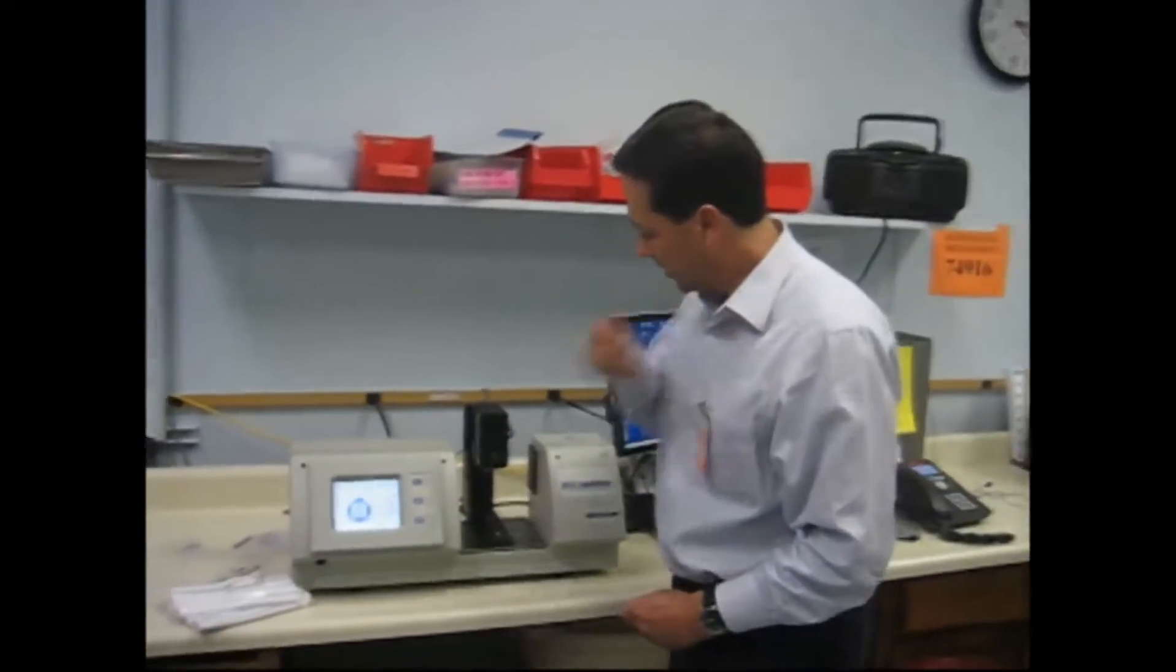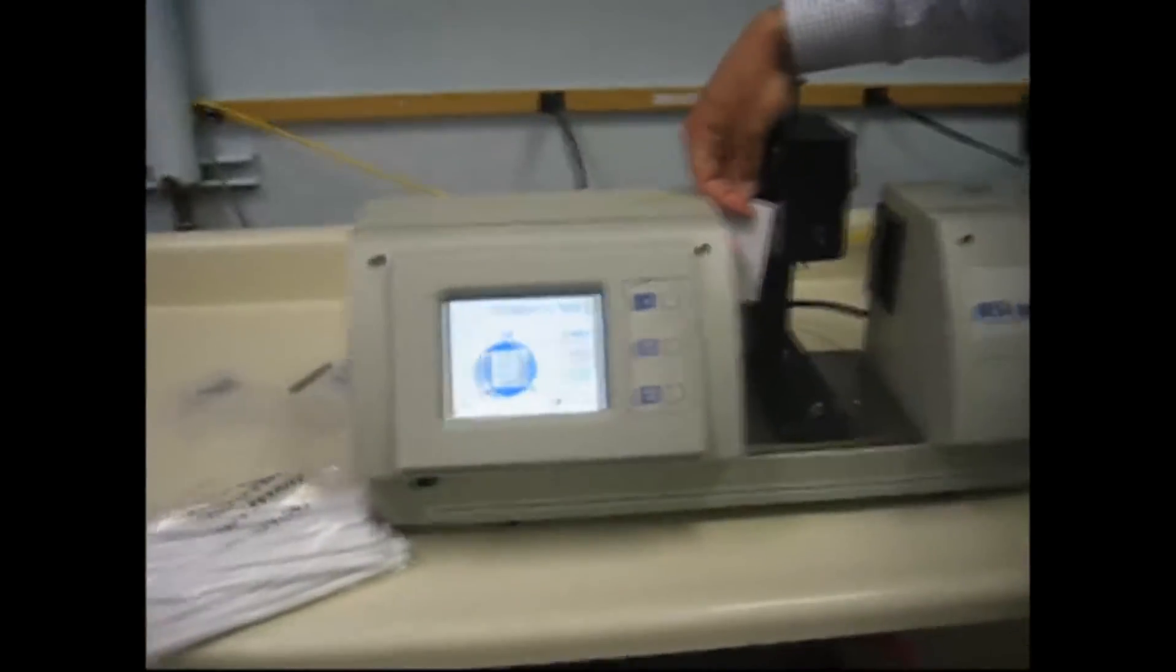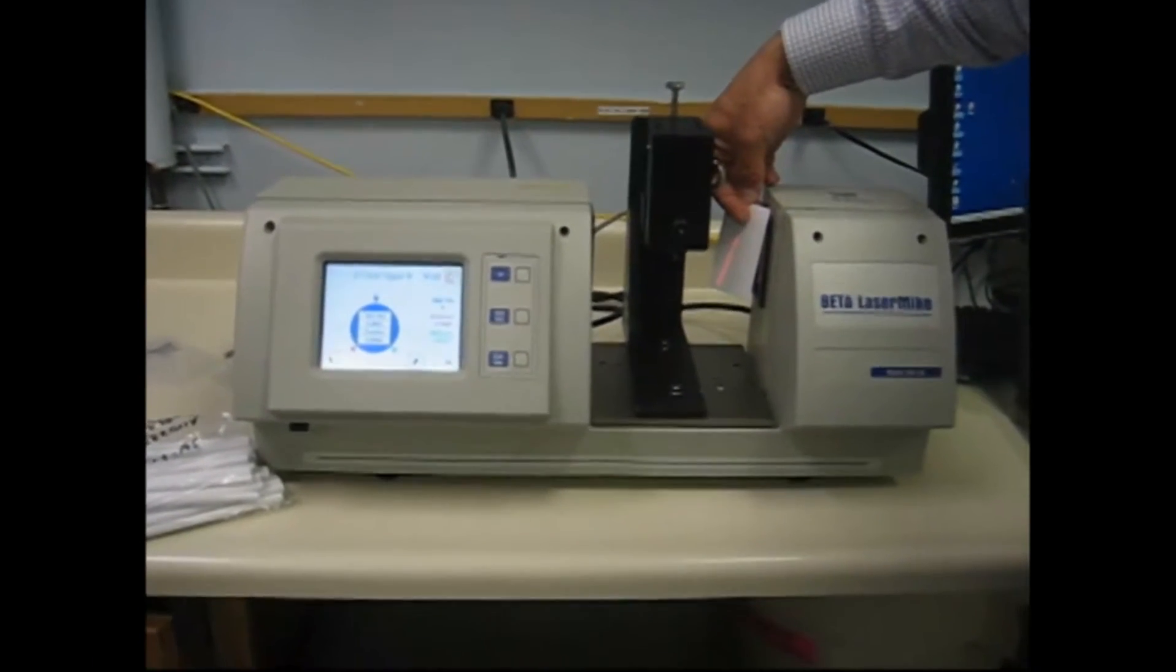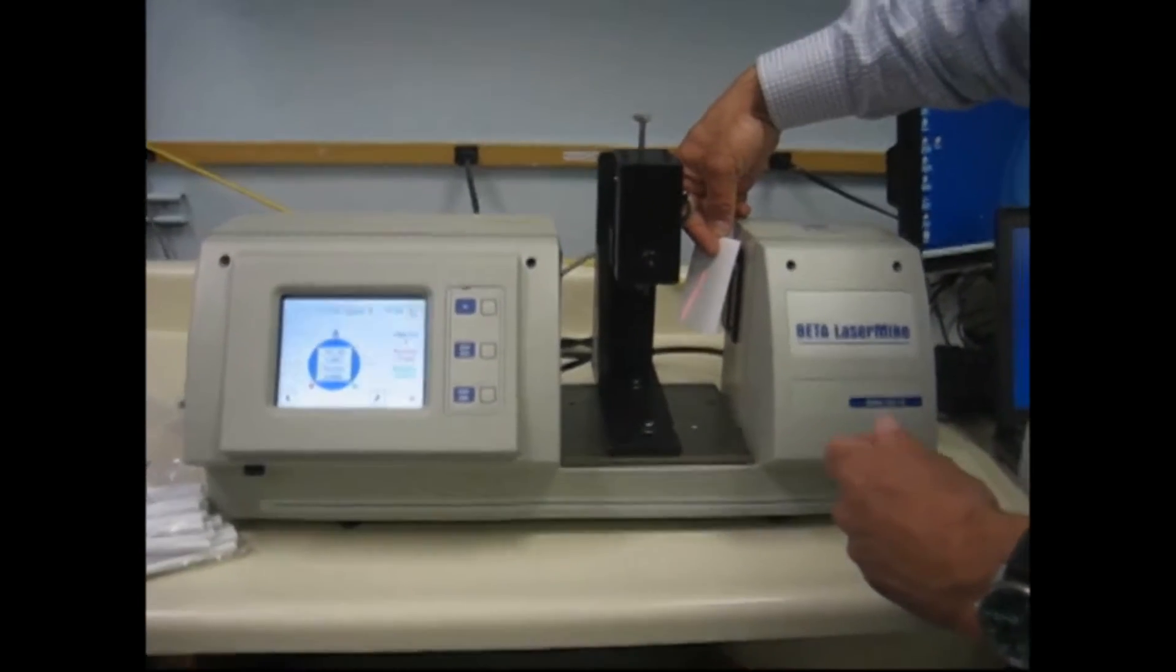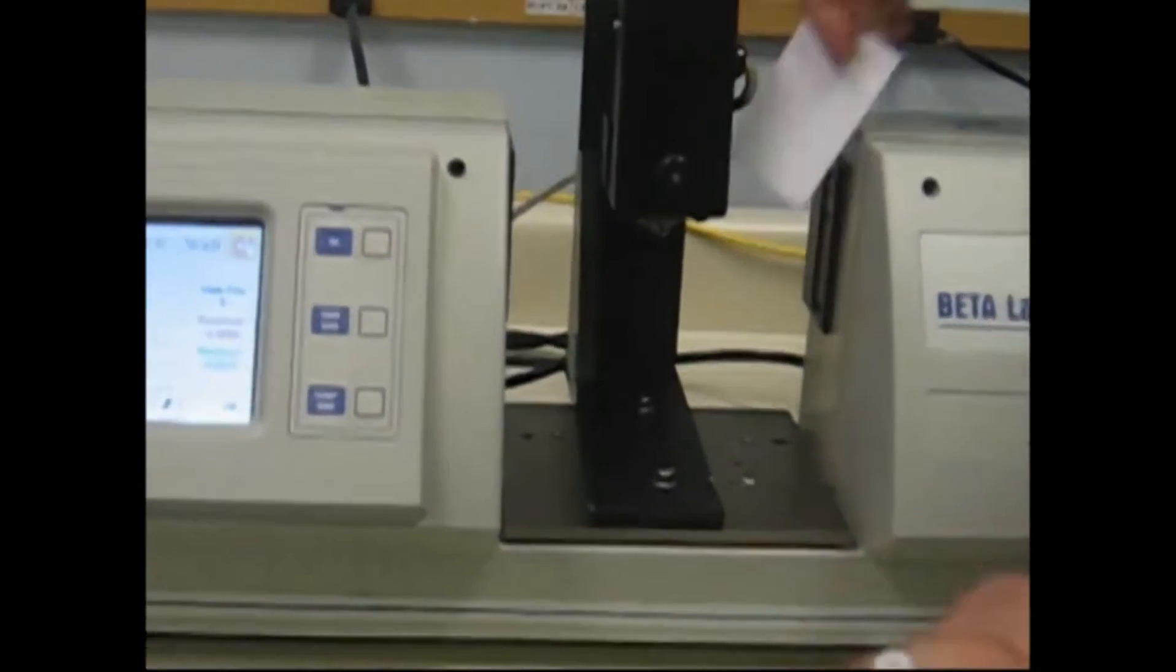The way it operates is it has a laser scanner across the air gap here. This is a two-inch laser beam. In that beam there's a mandrel, and what we do is we zero the mandrel out before we take a reading, whenever we switch the unit on, or whenever we change the mandrel due to product size.